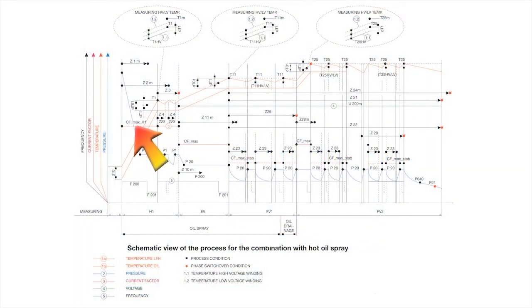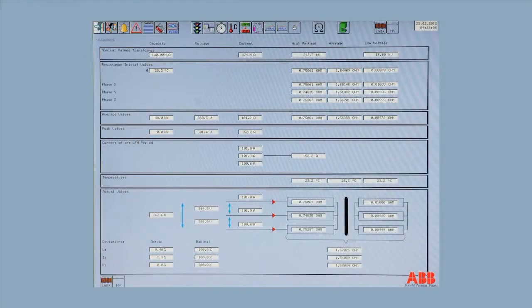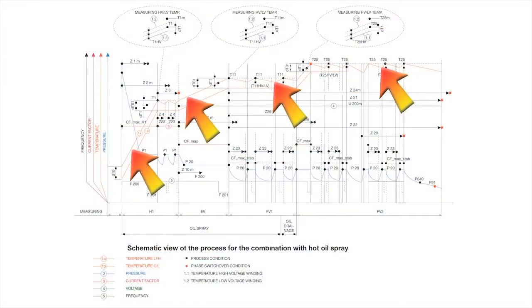The current factor has a maximum permitted value for the Heat 1 step and a maximum value for the remainder of the process steps. The current factor is controlled by the computer and is adjusted to meet the temperature rise requirements. The computer cannot exceed the current factor maximum set point values regardless of the heating outcome. The temperature of both the HV and LV windings are computed from the relationship derived in the measurement step between the resistances of the windings and their temperatures. An average temperature of all the windings for all of the HV and LV phase windings is also computed.